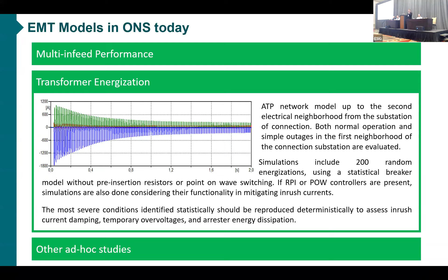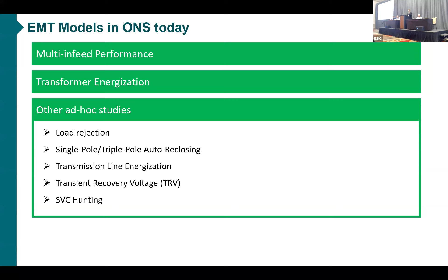So basically these two are the regular studies: PSCAD for the performance study, and ATP for equipment withstand capability study, like transformer energization. We also have other studies done on demand, such as load rejection, single and triple pole auto-reclosing (mostly single pole for EMT studies), transmission line energization, transient recovery voltage, and SVC hunting studies.